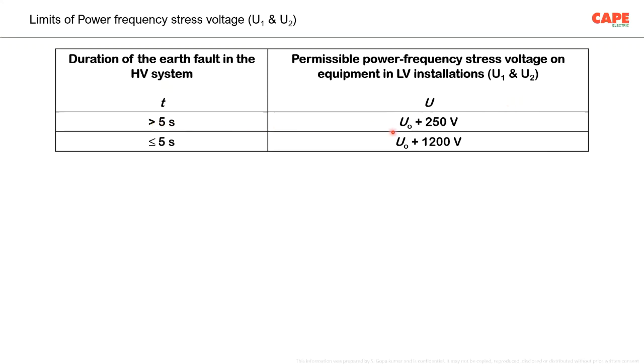More than 5 seconds, U0 plus 250 volt. I have a better table. I will show it later. Up to 5 seconds, U0 plus 1200 volt. What it means is that up to 1200 volt for 5 seconds can be experienced between a phase conductor and the earth in an electrical installation. This stress is the accepted level. Your equipment and your wiring must be able to withstand this particular stress.